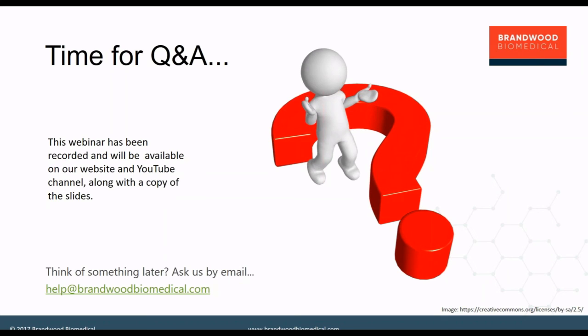I've got a question from Paul here. If in multiple languages, is there a requirement to include each language translation, especially for the IFU? Okay, so your technical file has to be put together with a view to meeting the local regulatory requirements in the relevant jurisdiction.